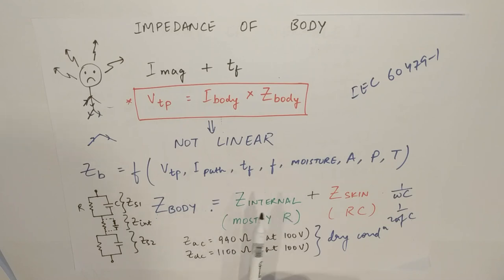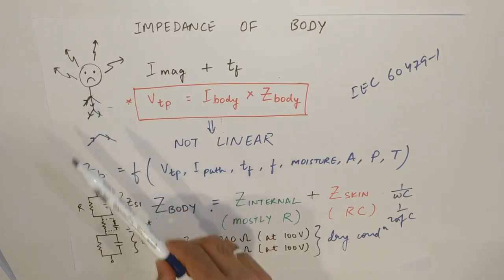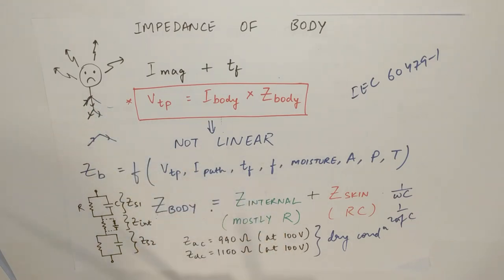Now, this body impedance is divided into two. One is internal. Then the other one is skin. It is the sum of both. Internal is mainly resistive part. And it is mainly due to the flow of current. It is not dependent on other factors. It is only dependent upon the path. Like it is going from hand to hand or from hand to leg, which is mainly the internal impedance. The skin impedance is comprised of both resistance and capacitance. And it is dependent upon the touch voltage, the duration, frequency, moisture, area, pressure, and temperature. Now, as you increase the touch voltage, there is a breakdown in the skin. And the value of skin impedance falls. It goes considerably low, making this body impedance only dependent upon the internal impedance.